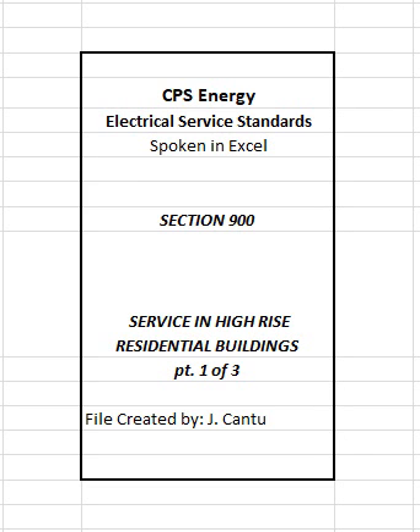902 CPS Energy service voltage supply. Service voltages will normally be supplied by CPS Energy from a three-phase pad mount transformer whose installation shall be in accordance with Section 1000 and Figure 1002. Voltage supplied by CPS Energy will be 208Y/120 volt, 4-wire Y system. Note: customer shall be responsible for providing the necessary load information to verify that all 3-wire, single phase loads taken for residential loads from this 4-wire Y system is balanced.